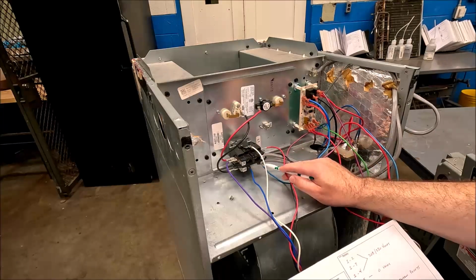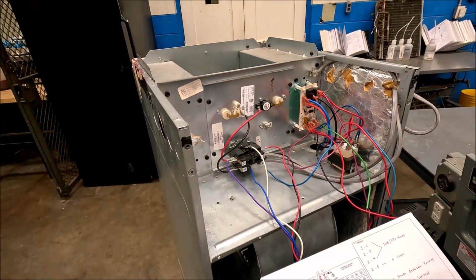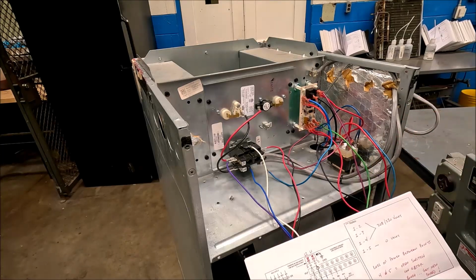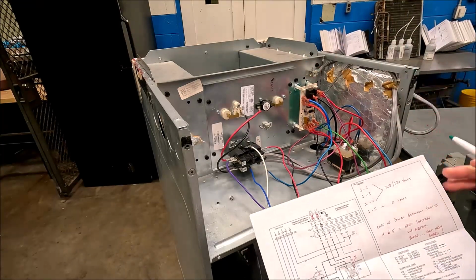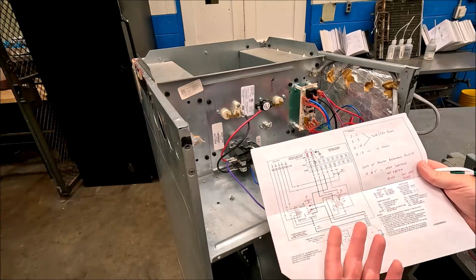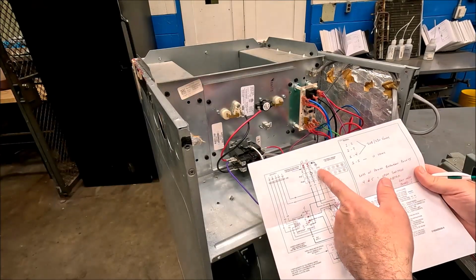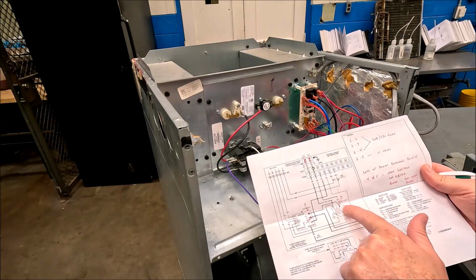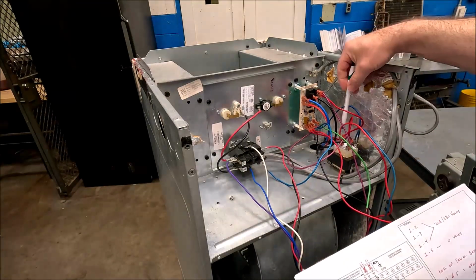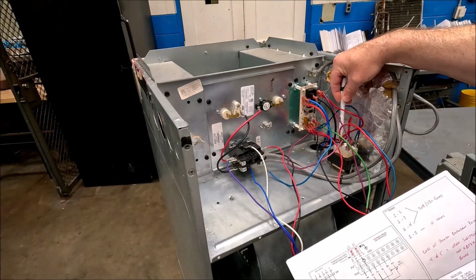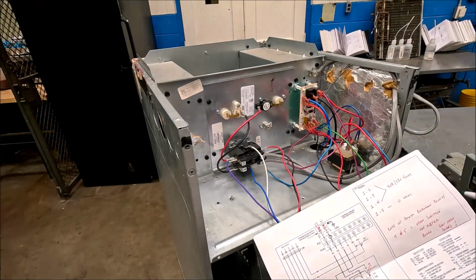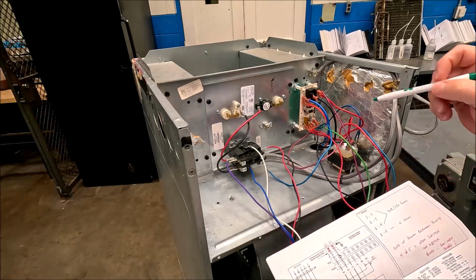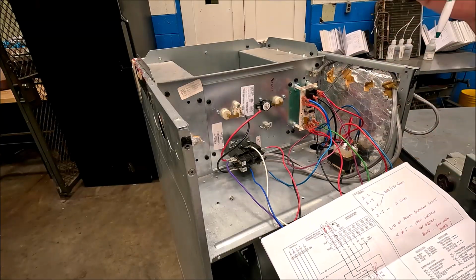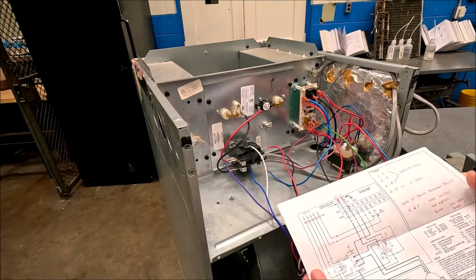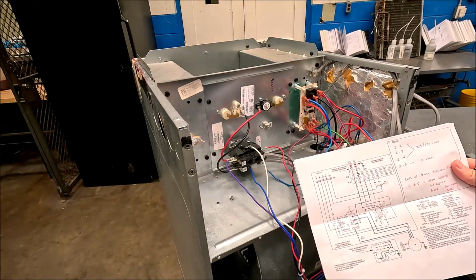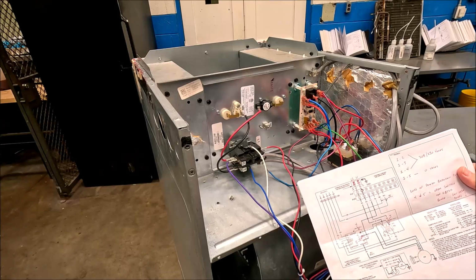So for me, L1, L2, I would label that 1 and 2. And if I'm troubleshooting whatever circuit, if I'm troubleshooting the blower motor, and that's what I've got my example here, I'm gonna choose number 3 to be a point in the L1 side, and it's gonna be right here for what I'm diagnosing, we'll say. But I will go through and I will number various points within one circuit. Now, by looking at the diagram, hopefully you get the mindset of what voltage is supposed to be there.